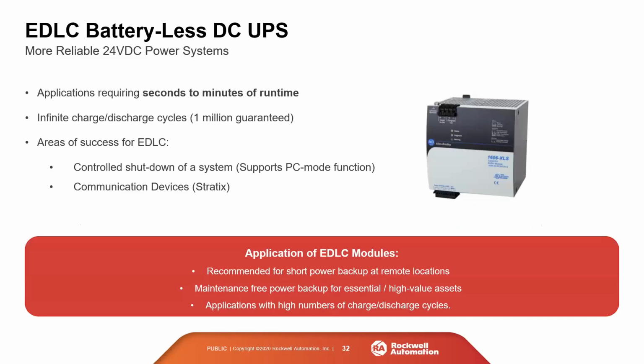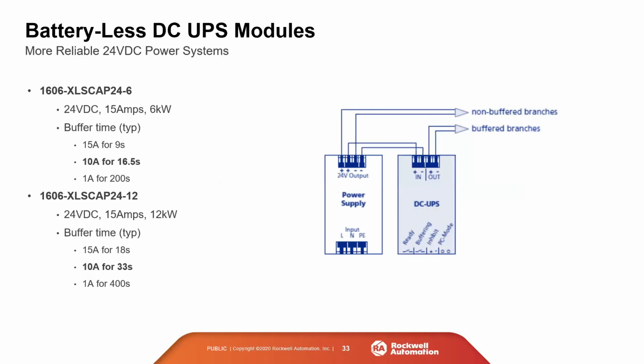Our EDLC battery-less DC UPS is for applications that require seconds to minutes of runtime. They have infinite charge-discharge cycles, so they're really good in applications where you expect to drop out and have to recharge a lot. They're also batteryless, which makes them really good in remote situations, because there's no maintenance on them. You don't have to go out and replace batteries or worry about whether your battery has enough charge. They're good for, I think they say, about 10 years before you really have to do anything, so it's a plug and play, set and forget kind of solution. These are just the part numbers showing some different specs.